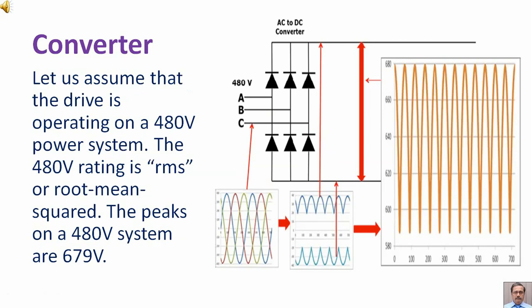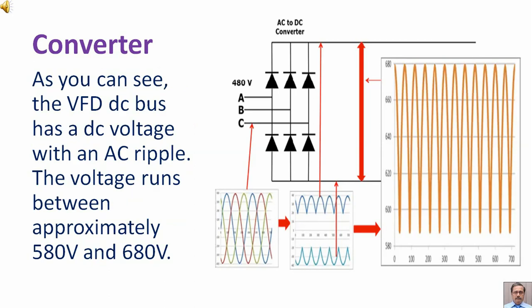Let us assume that the drive is operating on a 480 volt power system. The 480 volt rating is RMS or root mean squared. The peaks on a 480 volt system are 679 volts. As you can see, the VFD DC bus has a DC voltage with an AC ripple. The voltage runs between approximately 580 volts and 680 volts.